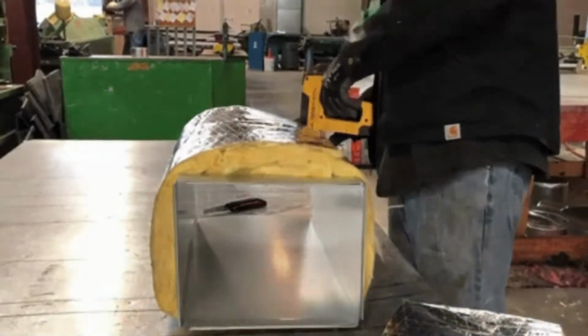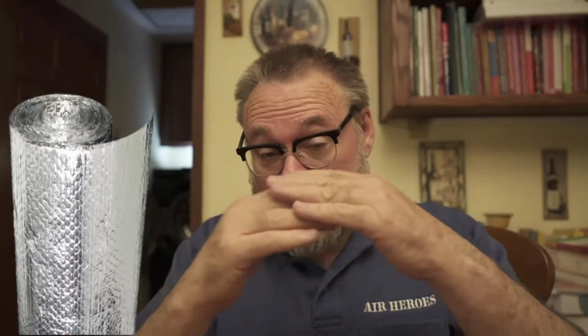That being said, we buy plenums all the time. And a lot of times when we buy them, they're already lined. We didn't think anything of it because my crew had been buying these plenums lined with a material called bubble wrap, or astrofoil, reflectix. There's a bunch of other names for this material. Basically, it's bubble wrap with foil pieces in between. One layer of it is supposed to give you an R value of 4.2. Two layers of it with an air gap is supposed to give you an R value of 6, and you can also get up to R8 with 2 wraps of it.